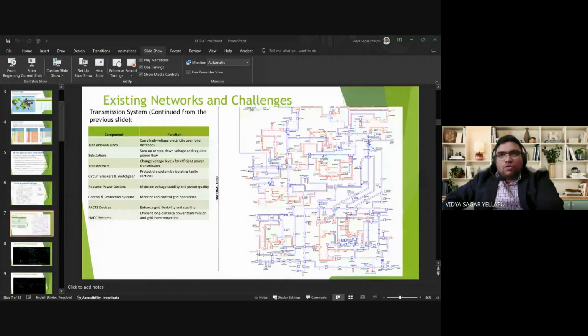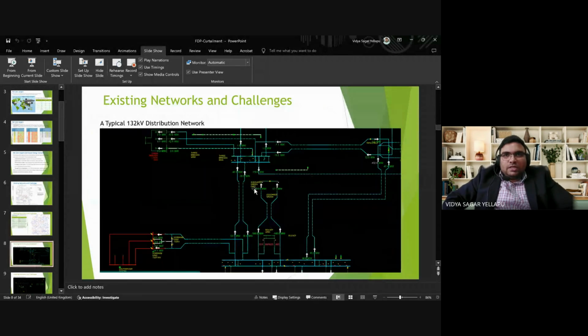And if we go further in voltage levels, so far we have seen the network from 400 kV to 275 kV. If we go further, we reach the distribution network. This is a typical distribution network having all the voltage levels, right from 132 kV. Here is 132 kV, this is the 33 kV network, and this is the 11 kV network. We can see some underground cables here, some overhead lines here. All this forms the distribution network.